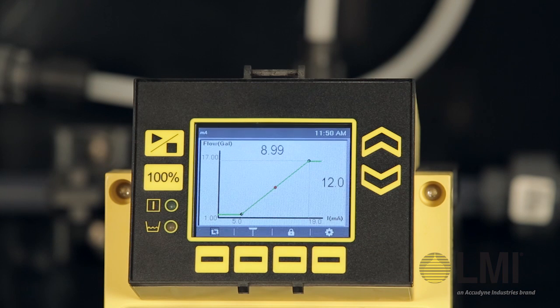As you can see, our chart has been updated and the parameters for the set points reflect the values we input. 5 milliamps at 1 gallon per hour and 19 milliamps at 17 gallons per hour. We are still reading 12 milliamps, but the pump is operating at 9 gallons per hour.